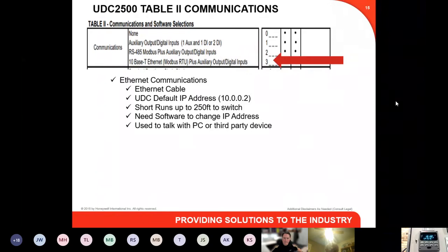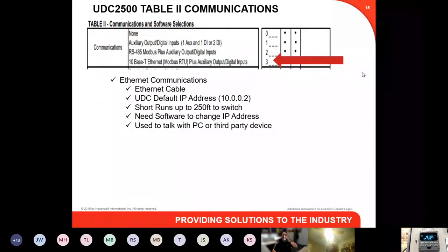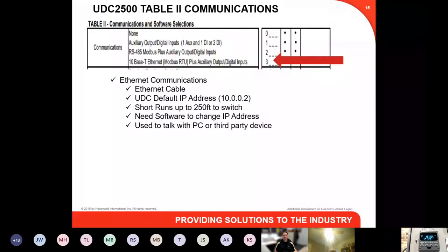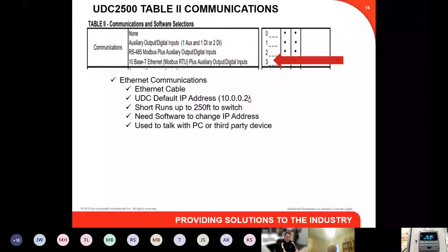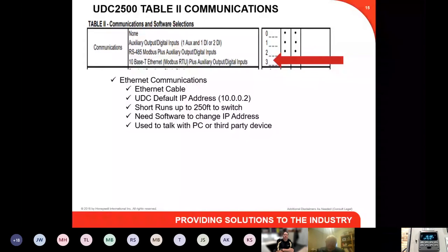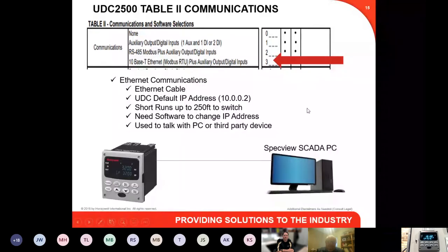Ethernet communications is a great way to get Modbus data back to a third-party PLC or PC with very fast communications. One thing to note: if you are changing the IP address — the default is 10.0.0.2 — you have to change it using Honeywell software that allows you to communicate to and program the UDC. It cannot be changed from the front face of the UDC, so keep that in mind when using the Ethernet communications.